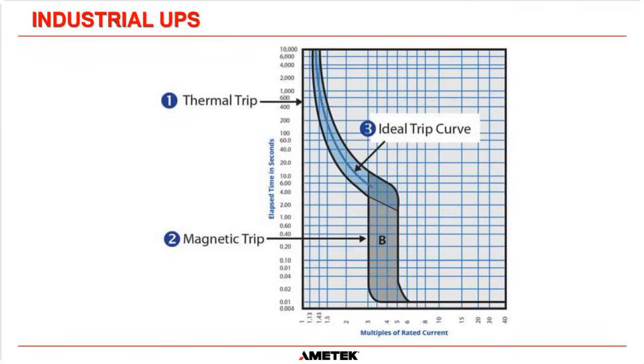Now, this is just a standard trip curve of a breaker. I can't even remember which model it was. But if it's a 10 amp breaker, we're saying we can only get 28 amps, which is 2.8 times the nominal rated current of that breaker. And if we follow that up, my terrible drawing, it's going to take 4 seconds for that breaker to trip on a 3-phase UPS. And if you have a short circuit on that load, that short circuit is probably going to pull down the inverter voltage, maybe to a level that is not suitable for your load circuits. Yes, you will transfer to bypass, but it's going to take anywhere between 0 and 4 seconds to do that.